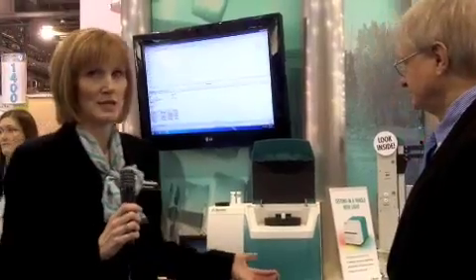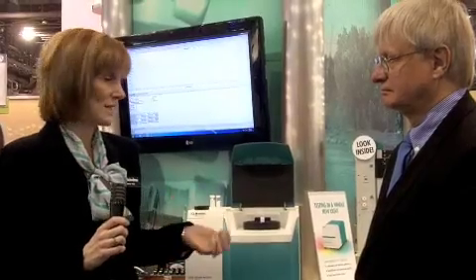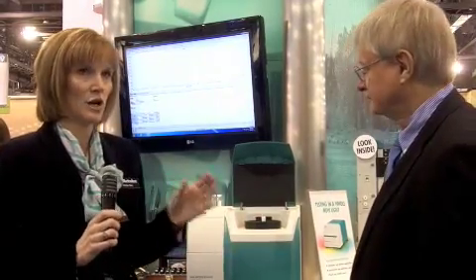Sure. The analyzer is based on the near-infrared region of the electromagnetic spectrum. We scan samples from 700 to 2500 nanometers. We also, with this analyzer, go a little bit further into the visible region, so from 400 to 2500 nanometers. And in the near-infrared region of the spectrum, we can see vibrations of carbon-hydrogen, nitrogen-hydrogen, and oxygen-hydrogen. So we're sensitive to organic compounds and anything with those types of bonds.